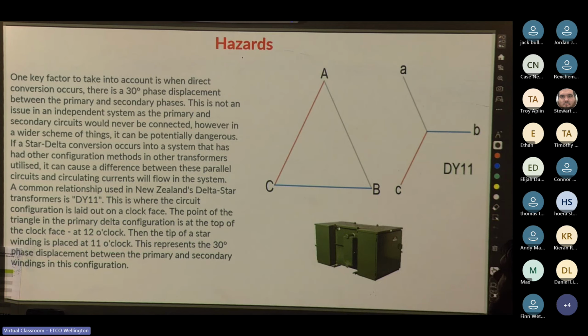Cool. So one key factor to take into account when direct conversion occurs is that there's a 30 degree phase displacement between the primary and secondary phases. This is not an issue in an independent system, as the primary and secondary circuits would never be connected. However, in the wider scheme of things, it can be potentially dangerous, because if it occurs in a system that has other configurations and other transformers, it can cause a difference between these parallel circuits, and we can get circulating currents in the system. Cool.